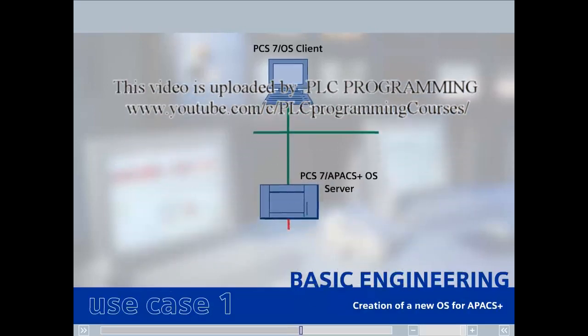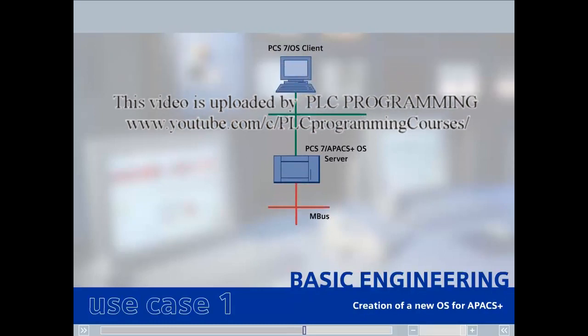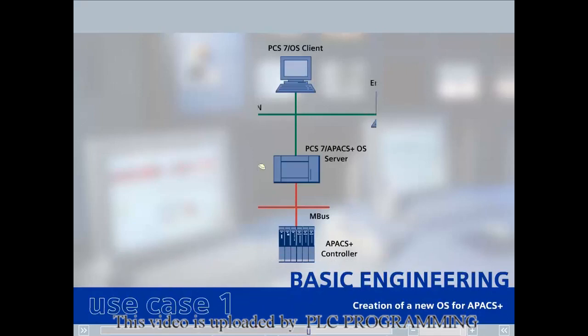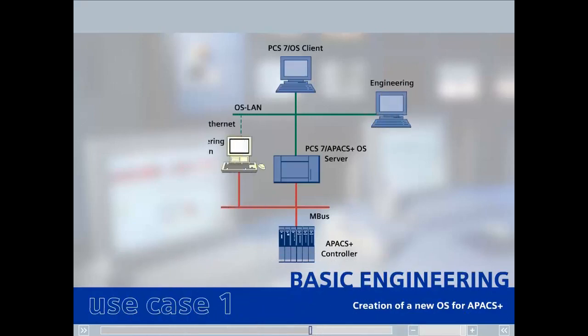The PCS7 APACS+ OS server is connected with the system bus, the M-Bus, and therefore has access to the subsidiary APACS+ controllers via the OS Ethernet network. The PCS7 OS clients are connected to the engineering system, and all engineering is done on the engineering system, from where the application software is downloaded to the server and the client.